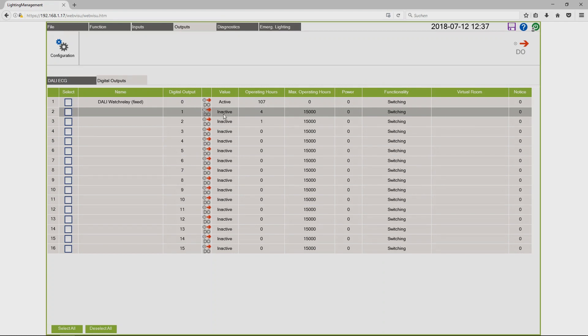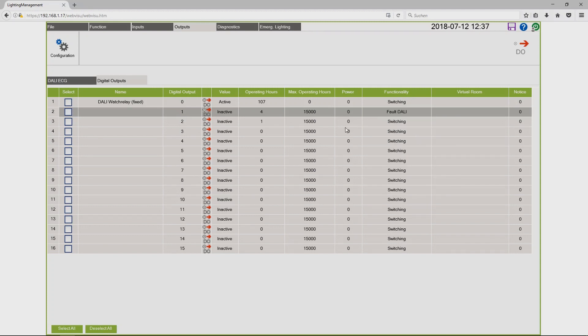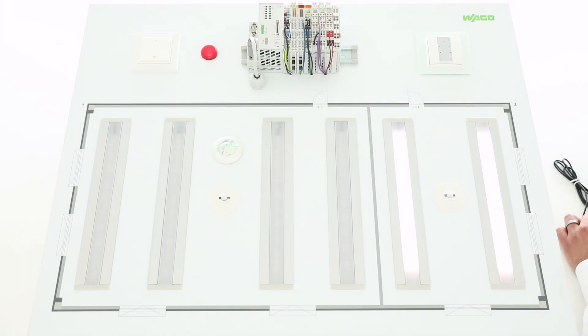I have prepared a failure. I have disconnected the DALI lamps from the DALI bus and I will now change the functionality from switching to fault DALI, and now you see the red lamp is blinking. That is a detected failure.